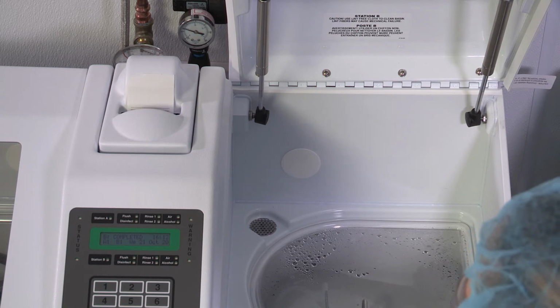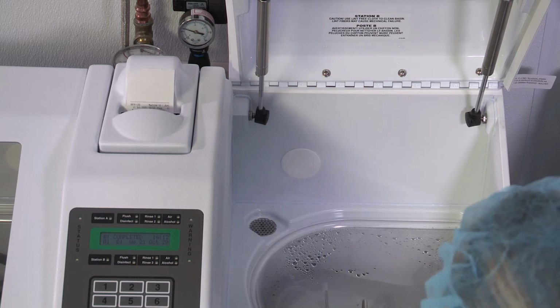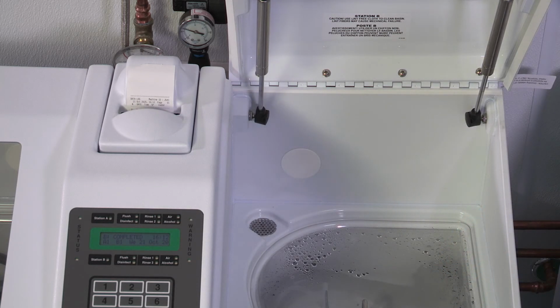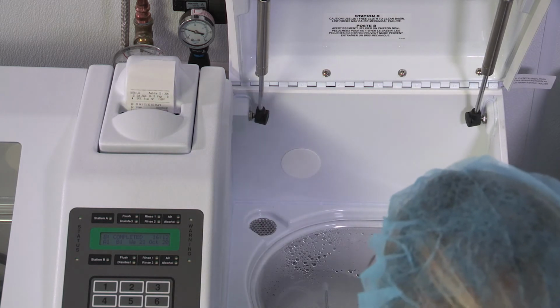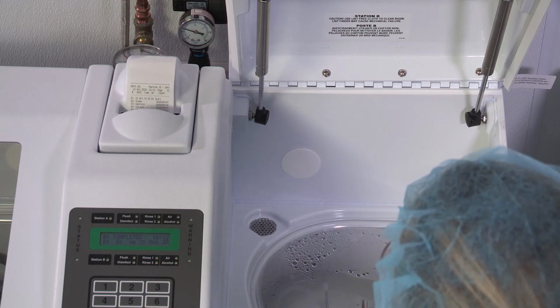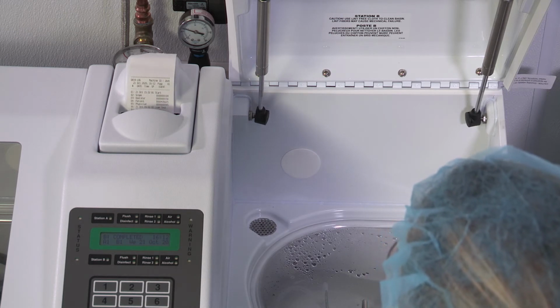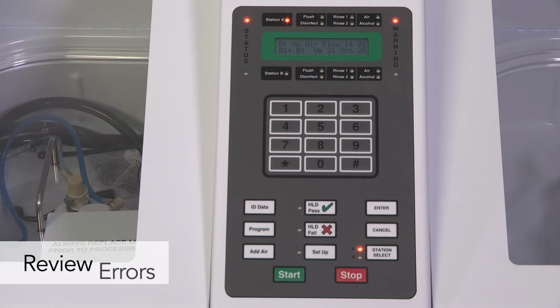Wait until the display shows Completed before disconnecting any hookup. If disconnected prior, the cycle indicates an error due to depressurization and the endoscope must be reprocessed. If the display shows aborted or an error message, review the errors and correct any issues so the endoscope can be successfully reprocessed. There is more information on correcting problems in the troubleshooting segment.